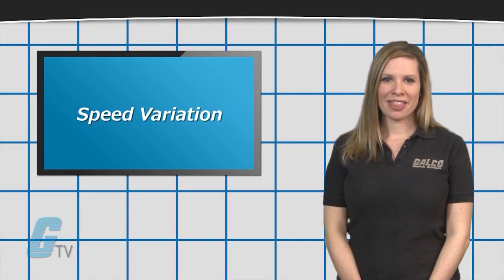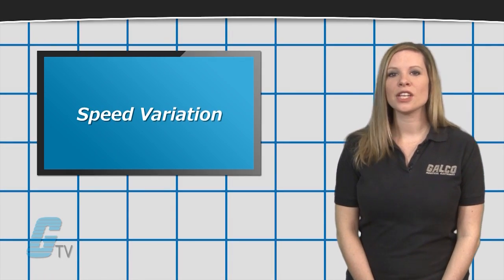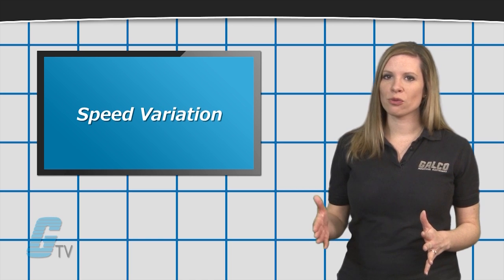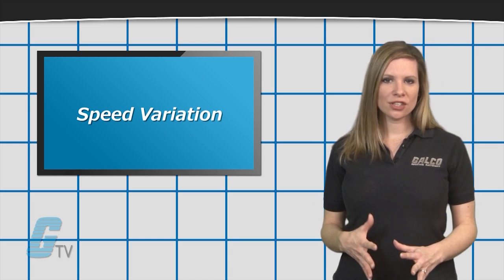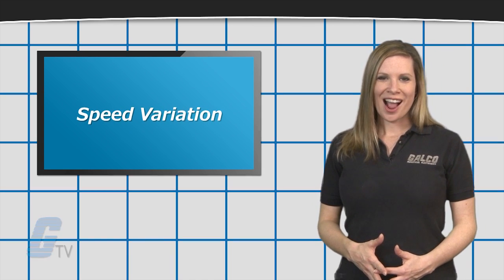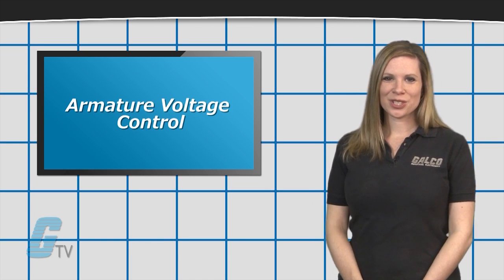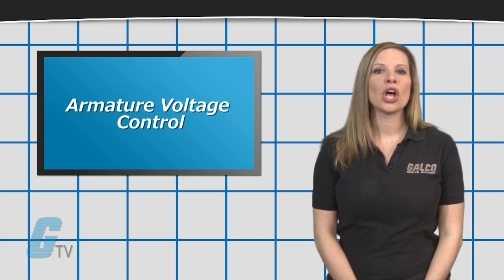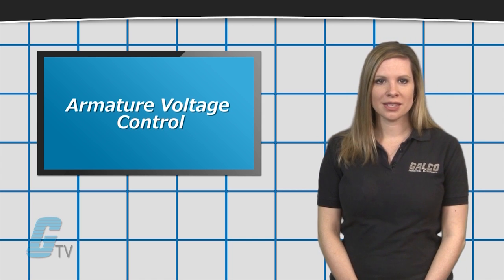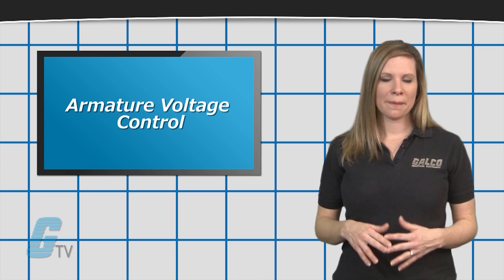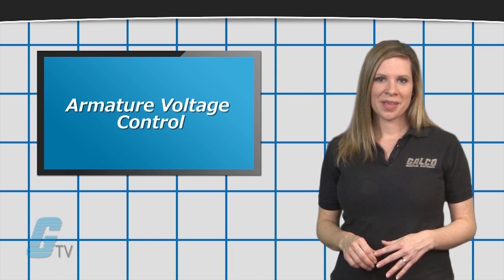Utilizing both methods of speed control will provide a wide variety of potential speed ranges. Armature voltage control is used for speeds below base speeds, which results in a constant torque capacity.